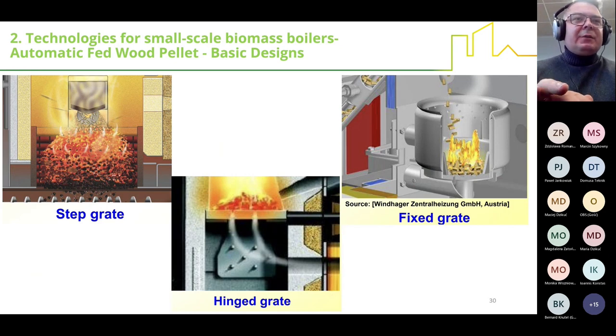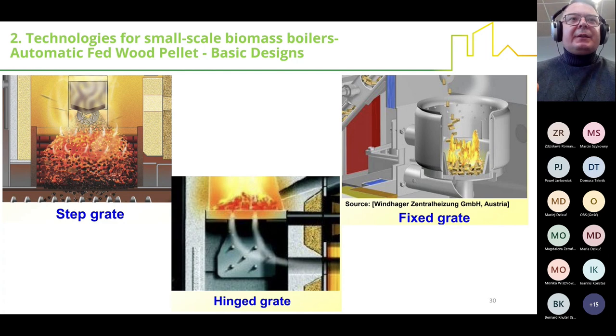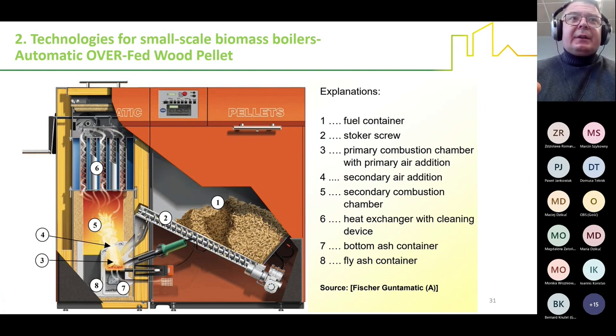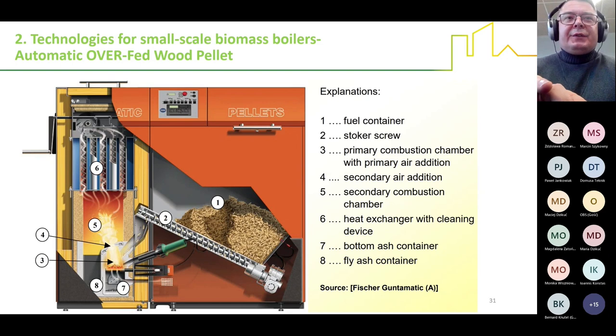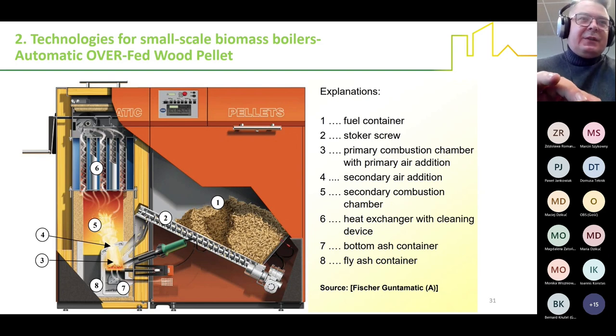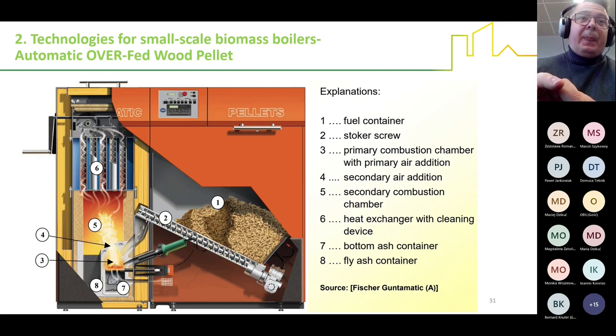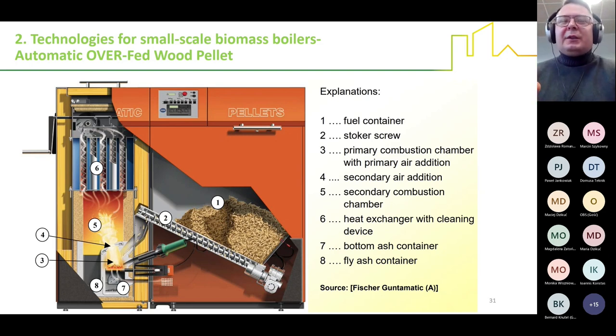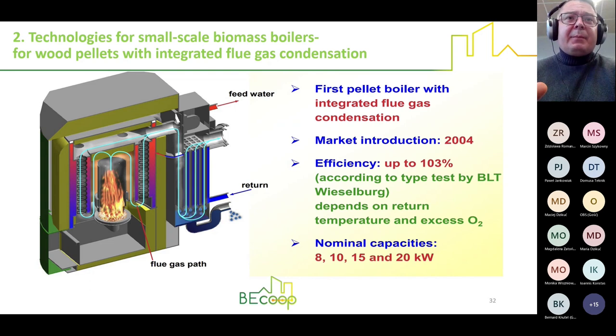A typical boiler system uses a retort furnace combined with under-feed burners. You can also have horizontal feed burners. It's all about the type of feeding and mixing system between air and biomass. All three systems have advantages and disadvantages. For feeding and combustion chamber types, there are step grate, hinged grate, and fixed grate systems. A typical pellet boiler includes a fuel container, stoker screw, primary combustion chamber, secondary air addition — which is very important for combustion efficiency — a heat exchanger section, and a bottom ash container.